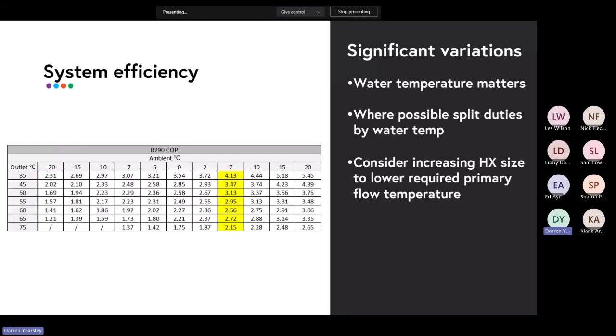And so if we're going into a system with a pool heating application, for instance, and we're replacing a gas boiler, and they've been running the gas boiler at 65 degrees and the plate heat exchanger is sized to do that, it makes a lot of sense to increase the size of that heat exchanger and lower the primary flow temperature down to 45. The additional efficiency you gain out of the appliance more than offsets the cost of increasing the size of the heat exchanger. So this is true in terms of heat exchangers for pool heating applications, air handler units, fan coils. Sometimes it can be well worth the trouble to increase the size of the coils to be able to lower the water temperature in the system.